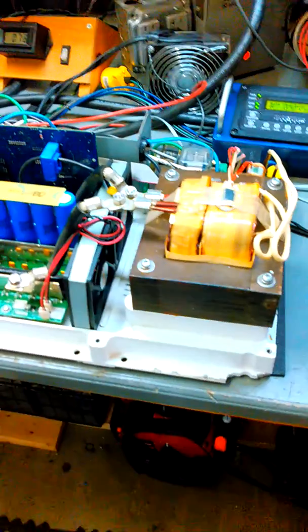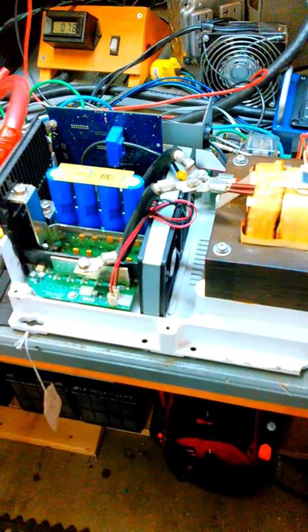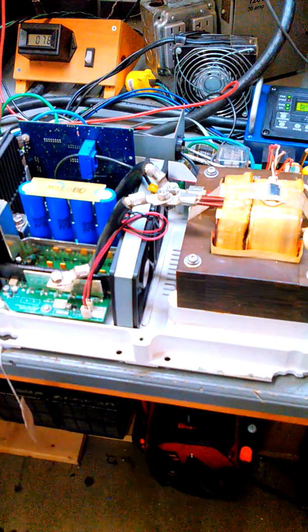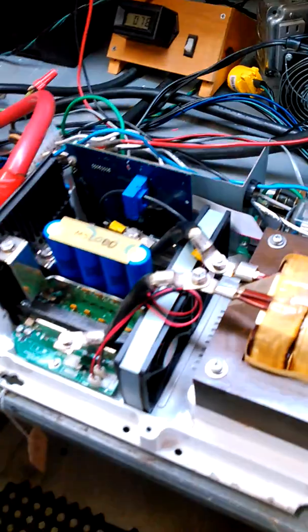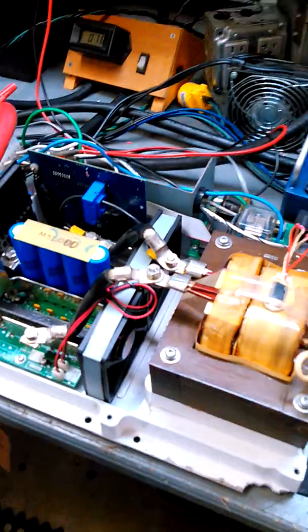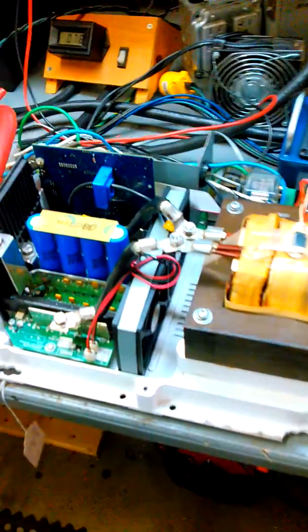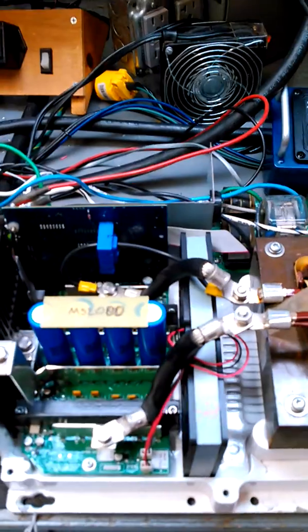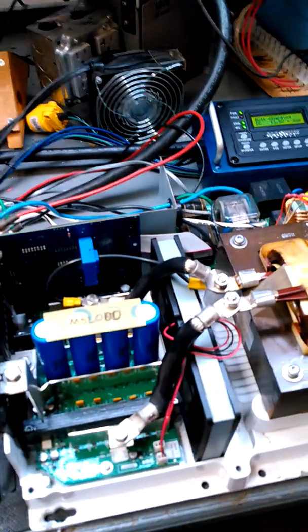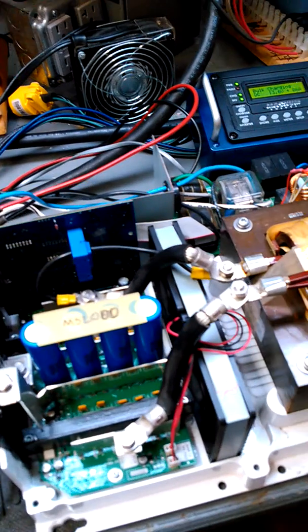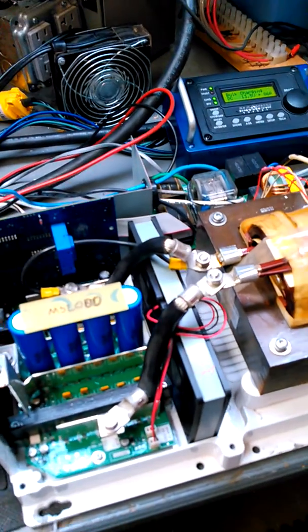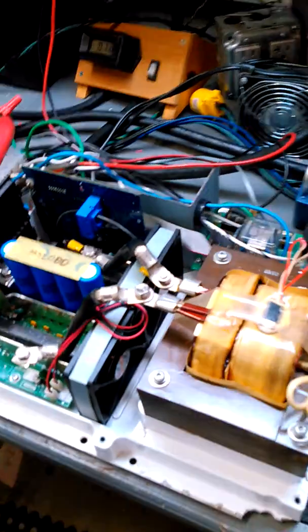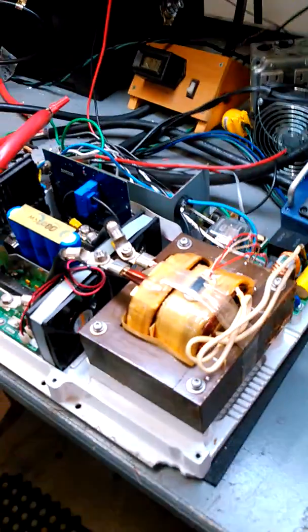This one was giving a false AC fault, and that's because the feedback cable has some corrosion on it. Had to clean and replace the cable, clean the corrosion off in the areas of the connector. Now it's working just fine.